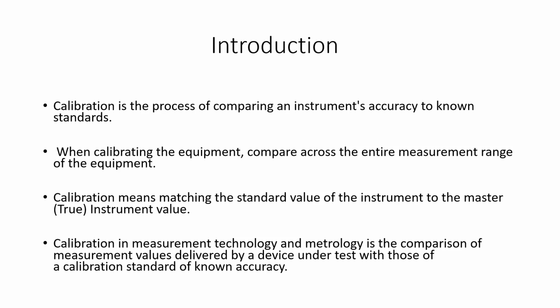Now, calibration is the process of comparing an instrument's accuracy. And how can you compare the accuracy of an instrument? You can compare it with the standard values. So a comparison between the instrument's values and the standard values is actually the process of calibration, right? When calibrating the equipment, compare across the entire measurement range of the equipment. That means you cannot just take one part or one range of the equipment's reading. You have to take from the start to the end. You have to compare each and everything, and by doing this you can get the value of the calibration for that equipment for the whole range, right?